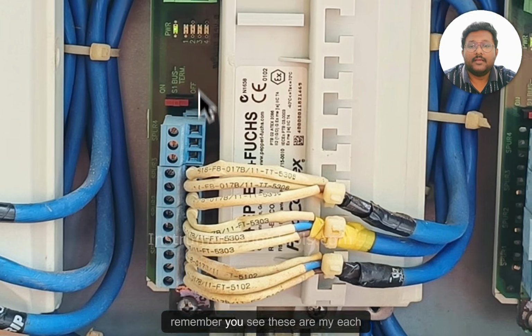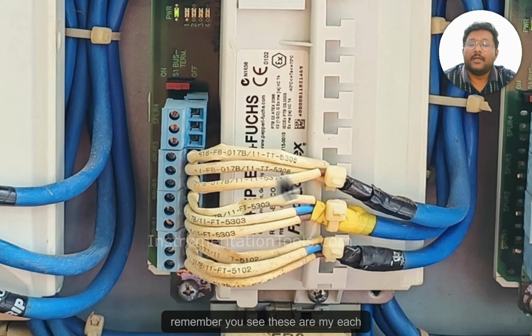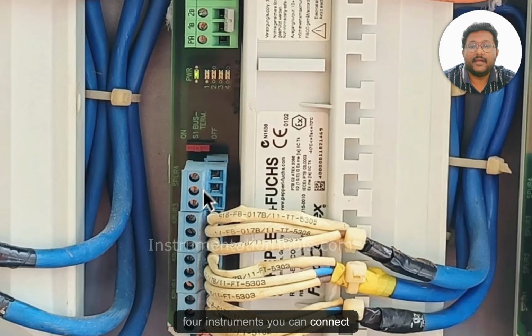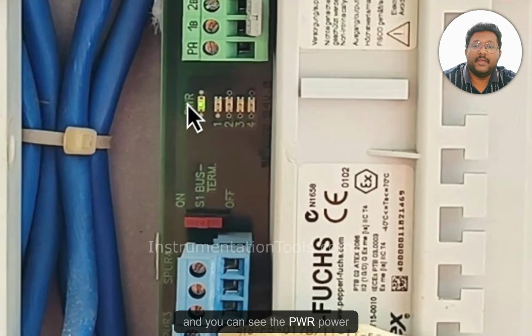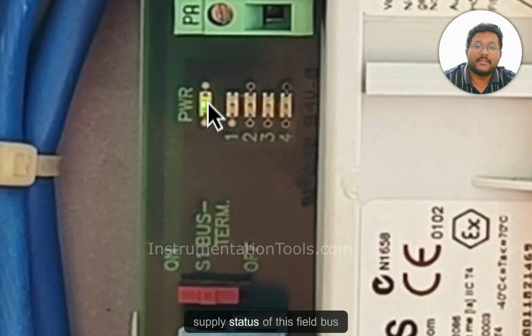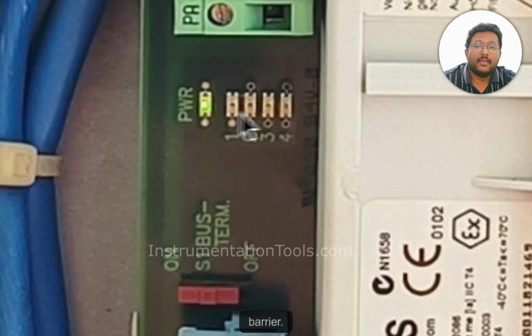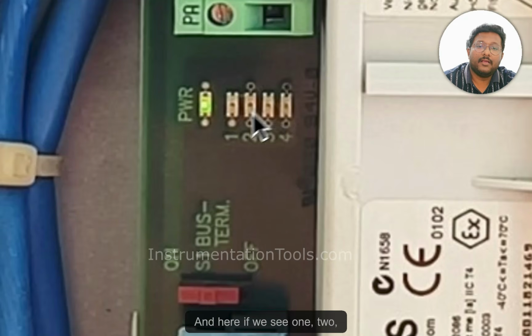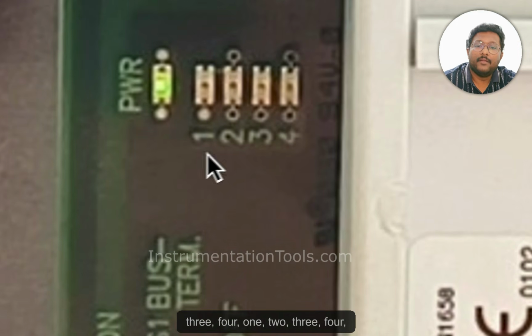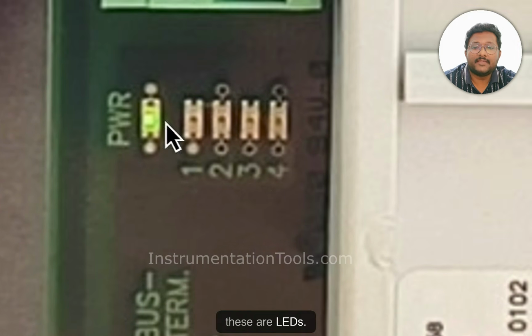Remember, each field bus barrier has 4 spurs, so we can connect 4 instruments, and you can see the PWR, the power supply status of this field bus barrier. Green means healthy. Here you see 1, 2, 3, 4, 1, 2, 3, 4, these are LEDs.